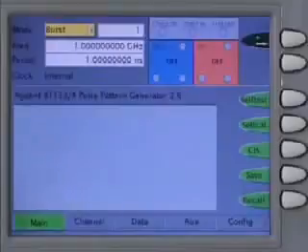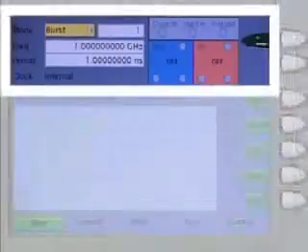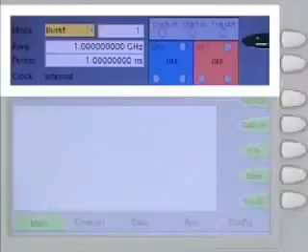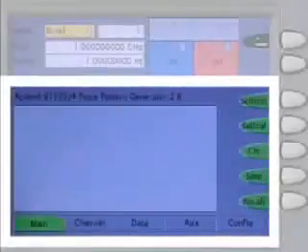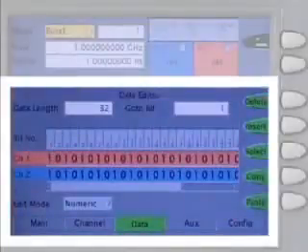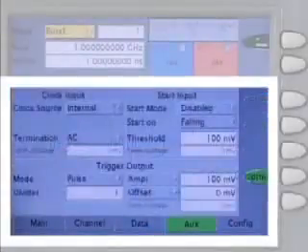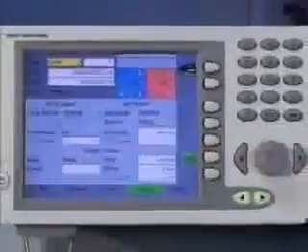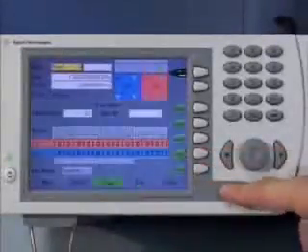The Agilent high-speed pulse and pattern generators are easy to use as they come with a self-explanatory graphical user interface. The top of the display always shows the main system settings, including operating mode and frequency. The lower part of the graphical user interface provides access to several submenus. In all menus, the important features and values can be directly accessed using the soft keys, which are located on the right-hand side of the display.